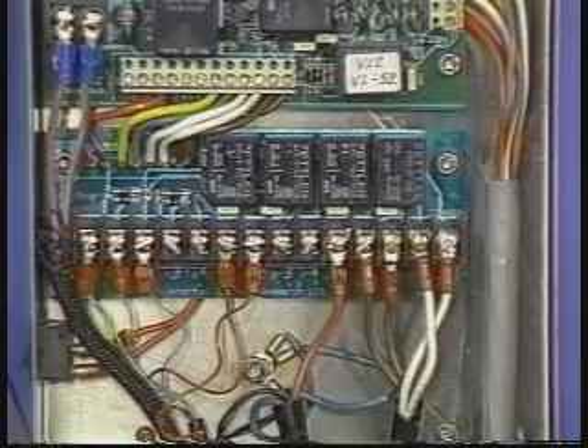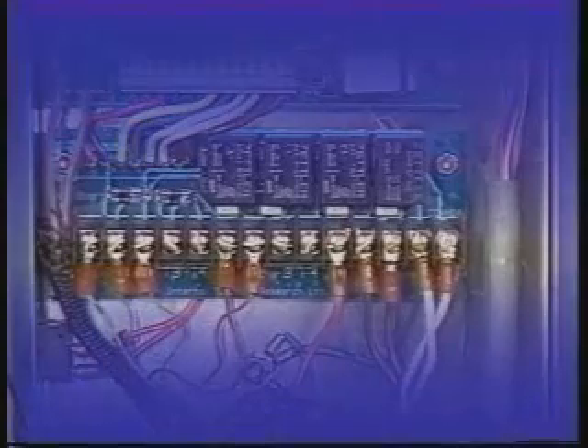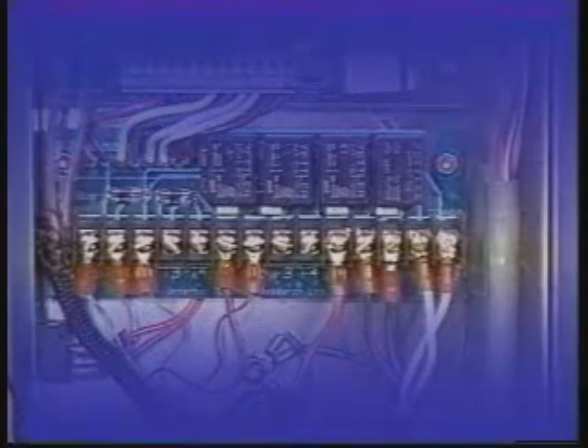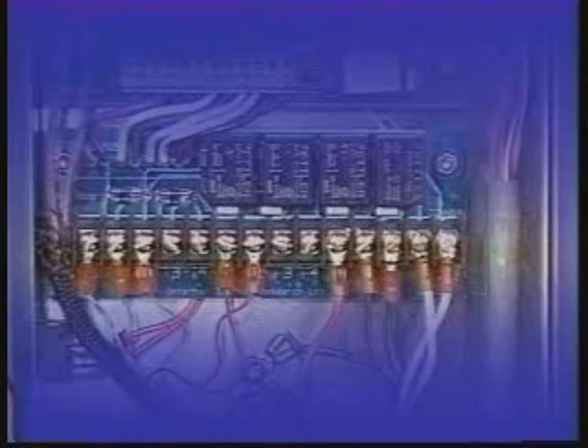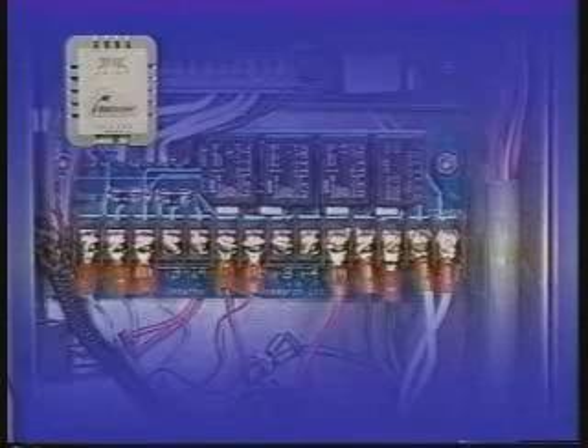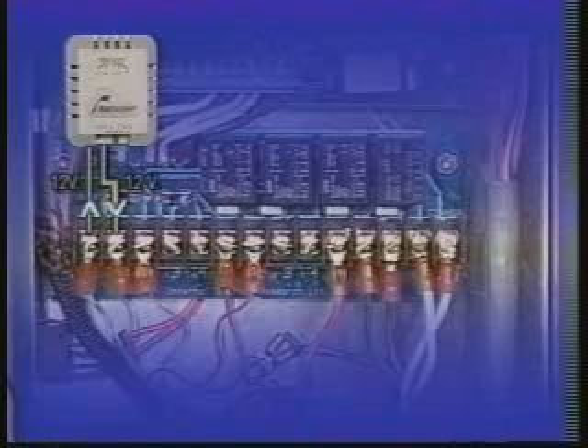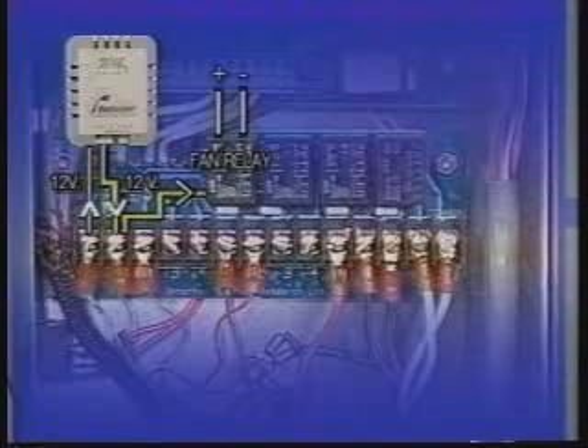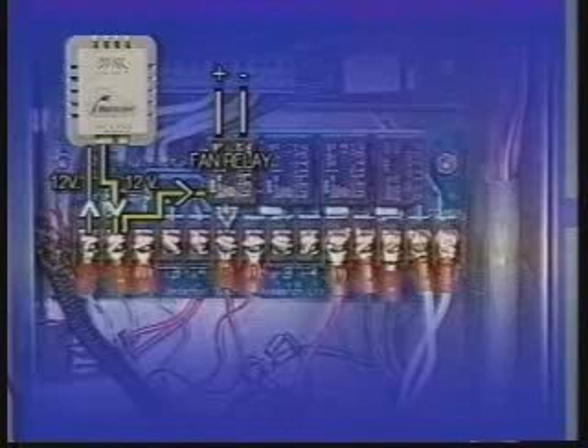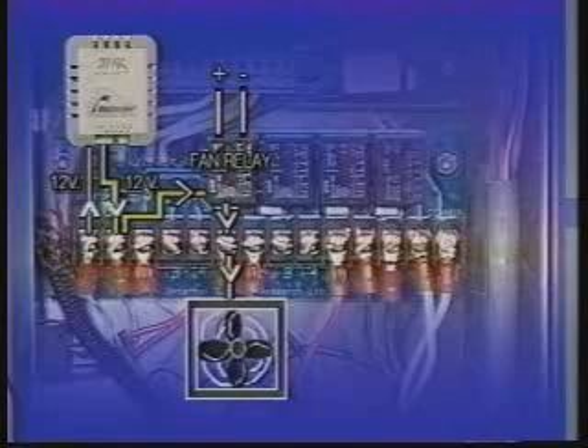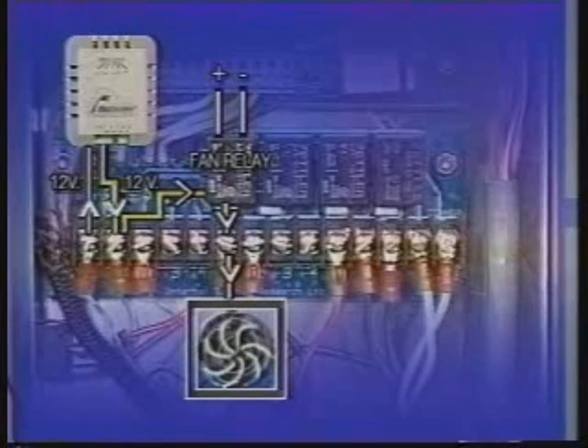Let's look at the operation of the circuit board. Assume that there is a 4-zone board installed. When the thermostat calls for heat, a circuit is completed between the thermostat common, TC, and the affected zone. This sends system voltage from TC to the zone, which engages the signal side of the zone relay and energizes the associated fan circuit, sending voltage to the air fans in the operating zone. The fan will run and the furnace will cycle as long as the thermostat calls for heat.